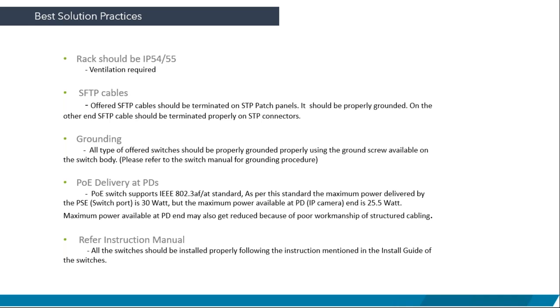The third point is that all the switches offered in the outdoor solution should be properly grounded, because there may be chances of a surge being induced from the outside. That surge should be grounded so that the switch gets protected. There will be one screw on the switch body, which should be grounded to the earthing through the outdoor rack.